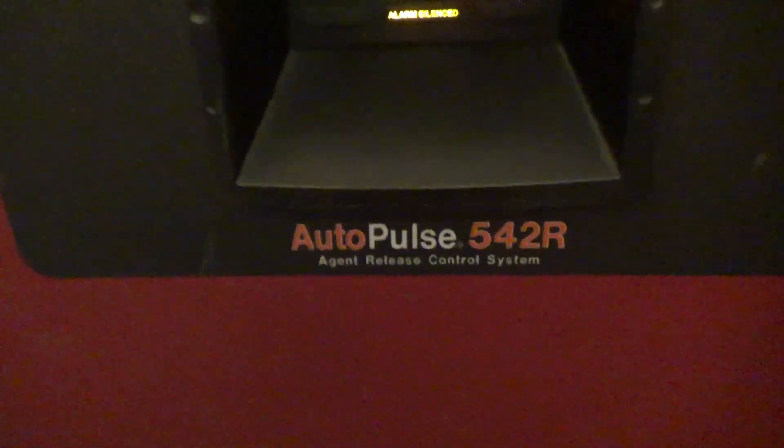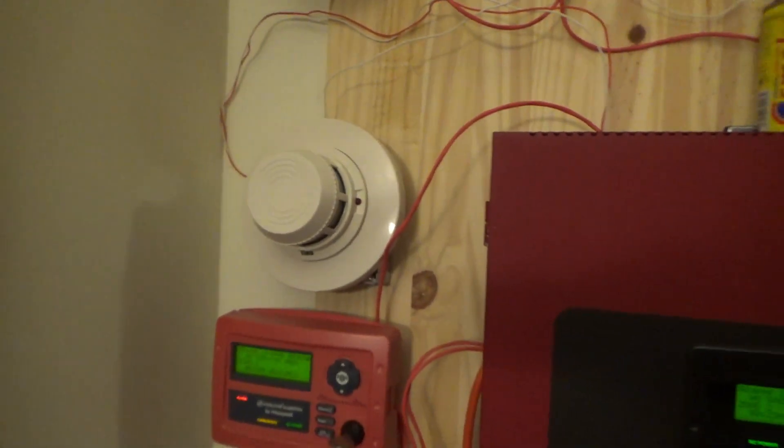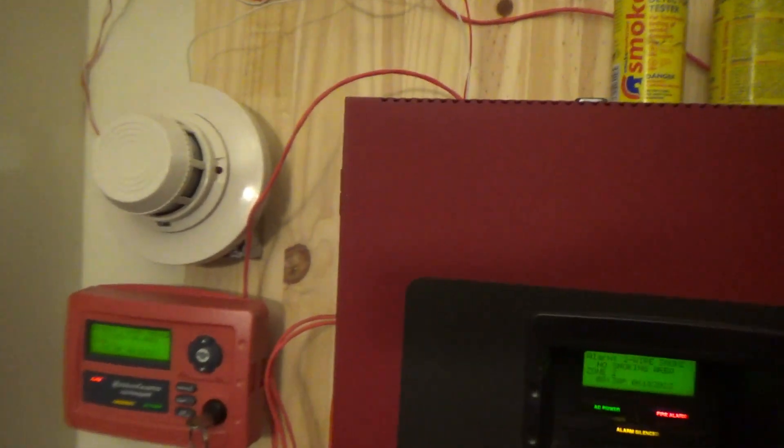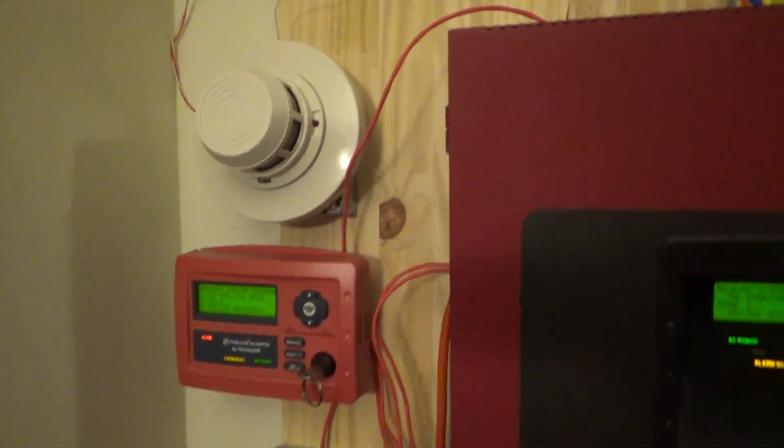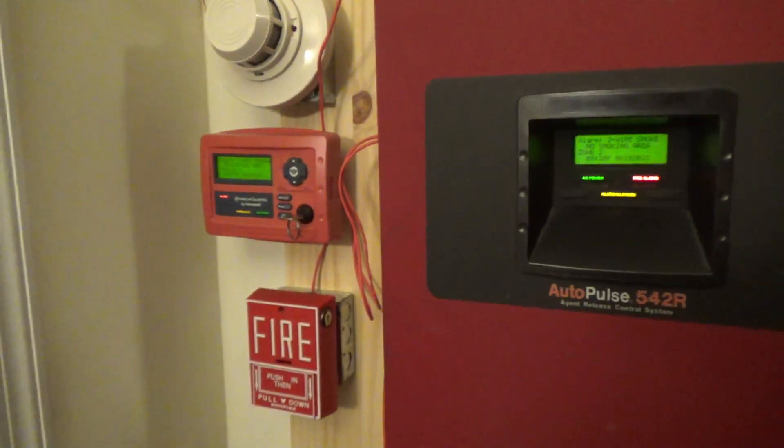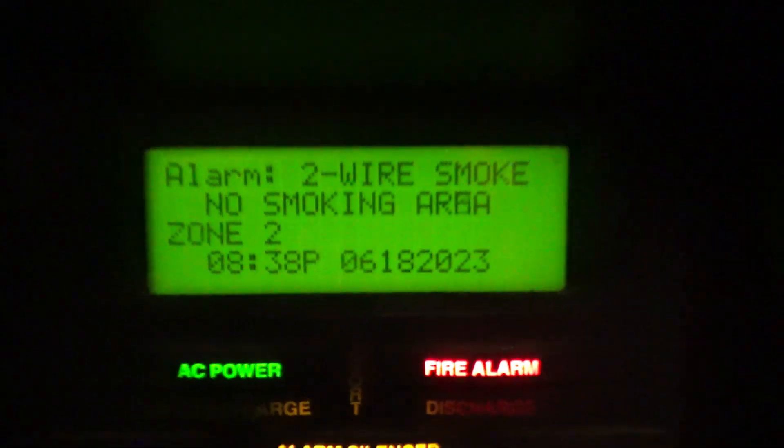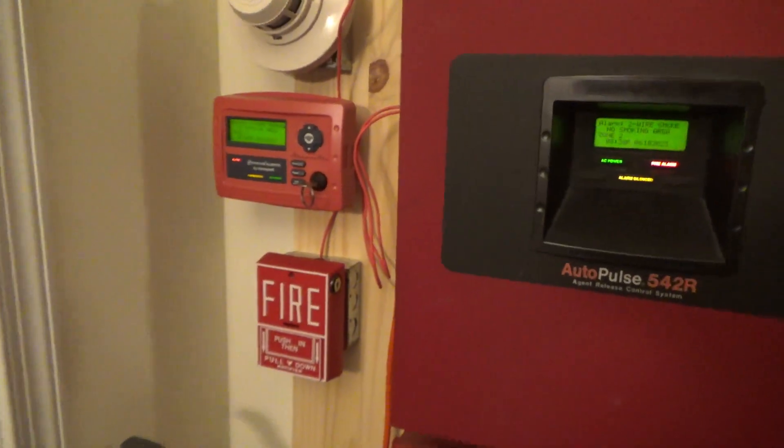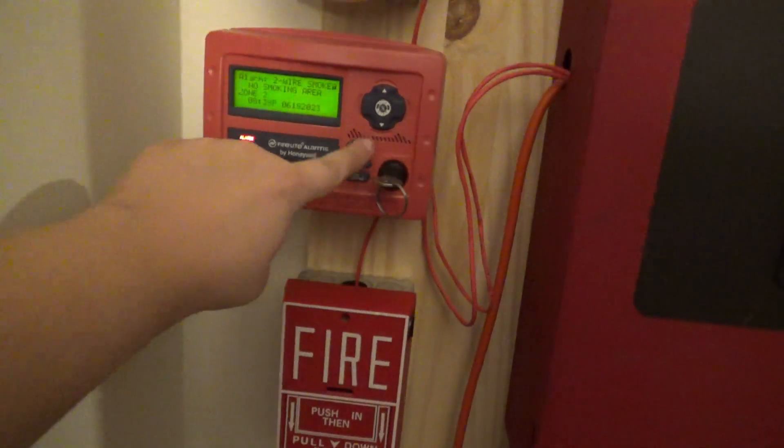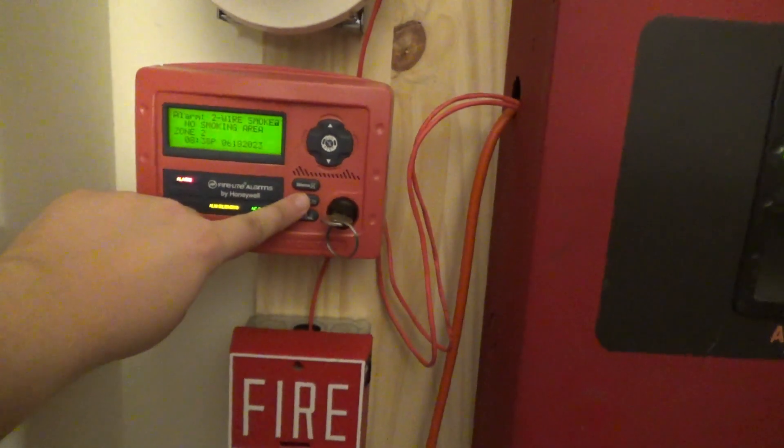Yeah, I'll probably have to change the smoke detector again because I'm not sure what's wrong with this one. As you can see, Zone 2 says two-wire smoke, and it is a two-wire smoke detector. Alright, let's go ahead and put a reset in the system, and then we'll call it a night.